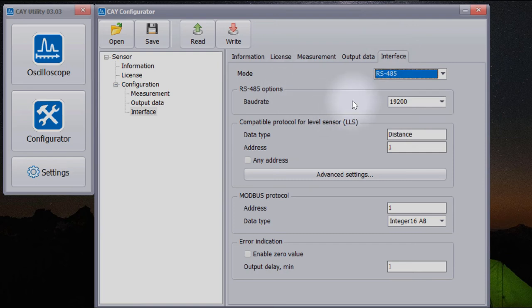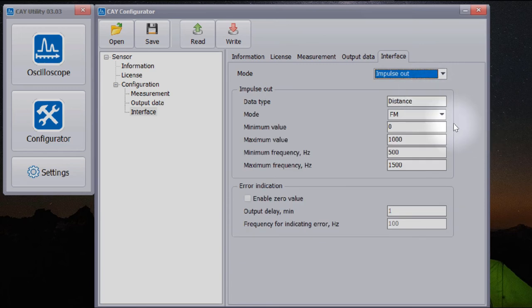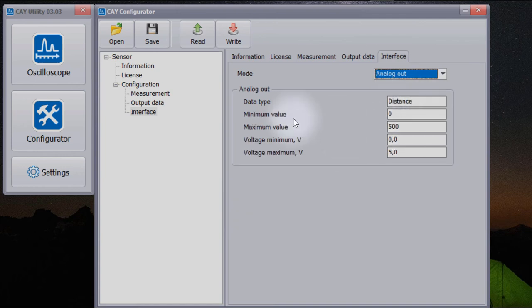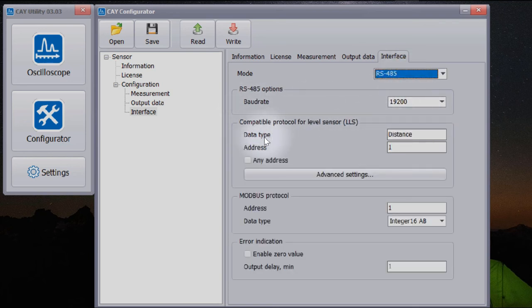At this step, you can choose an interface of the sensor: RS485 digital interface, or frequency interface with different modulation types, frequency and pulse width modulation. Minimum frequency will correspond to minimum level. Maximum frequency corresponds to maximum level, which you can set up as well. Also, we can set if zero value is restricted or not. You can also use analog voltage output in the range from 0 to 5 volts. We can set as well minimum and maximum values and corresponding output voltages.